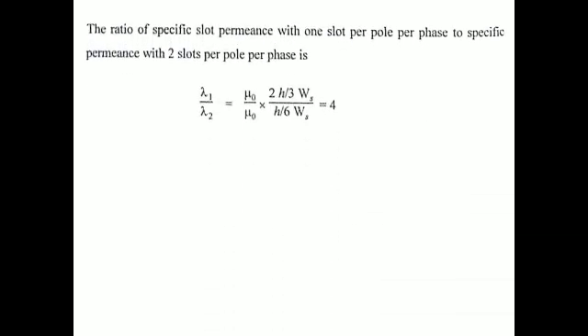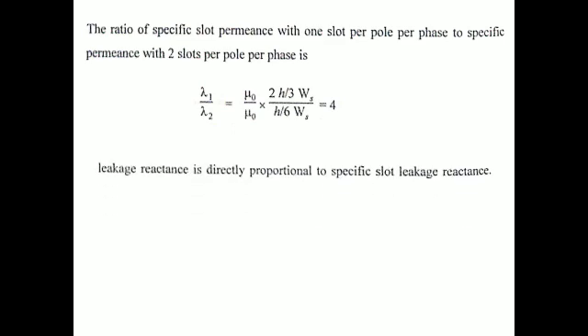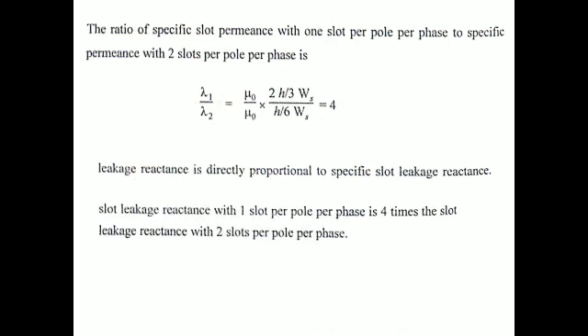We calculate the ratio λ₂ / λ₁ — note: λ₂ is one slot per pole per phase and λ₁ is two slots per pole per phase. After substituting and simplifying, all terms cancel and the final value becomes 4. So λ₂ / λ₁ = 4. The conclusion is: slot leakage reactance with one slot per pole per phase is four times that with two slots per pole per phase, since leakage reactance is directly proportional to specific slot permeance.